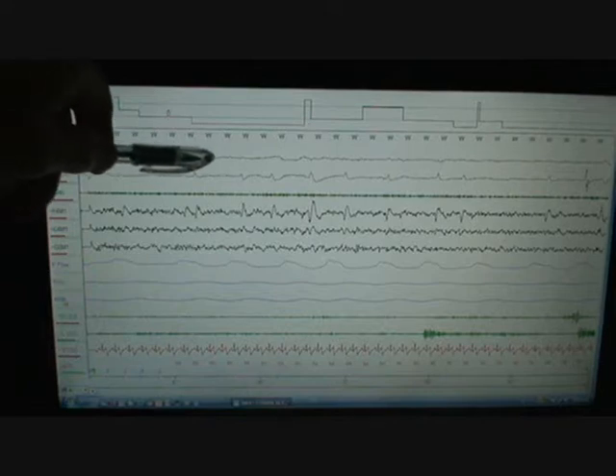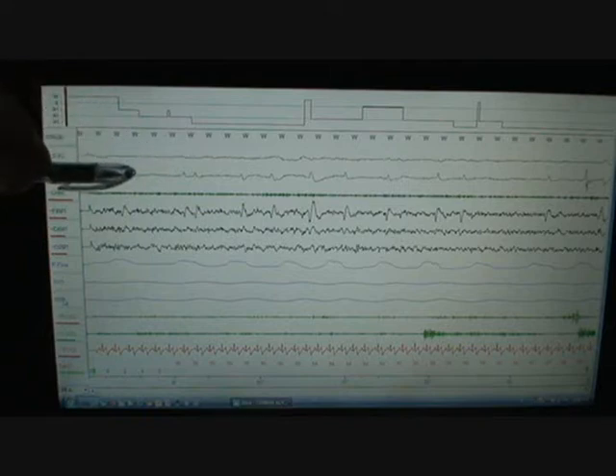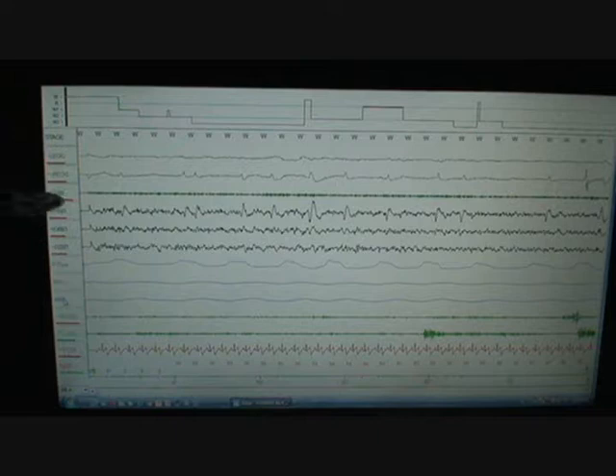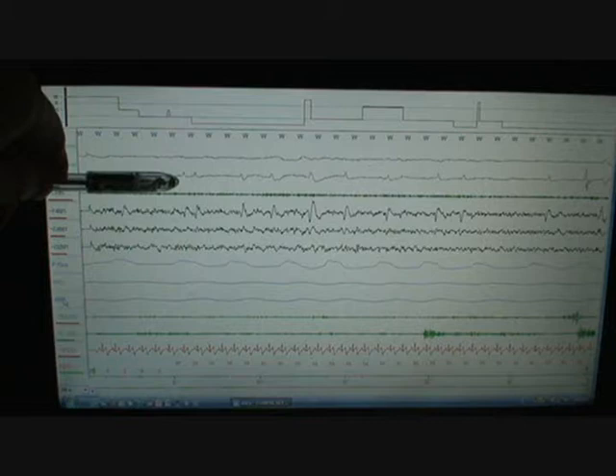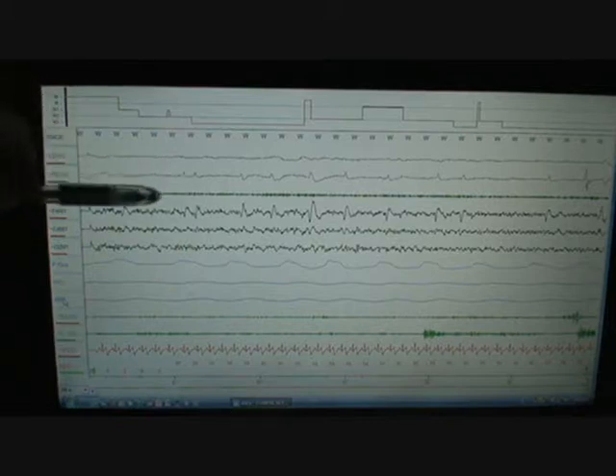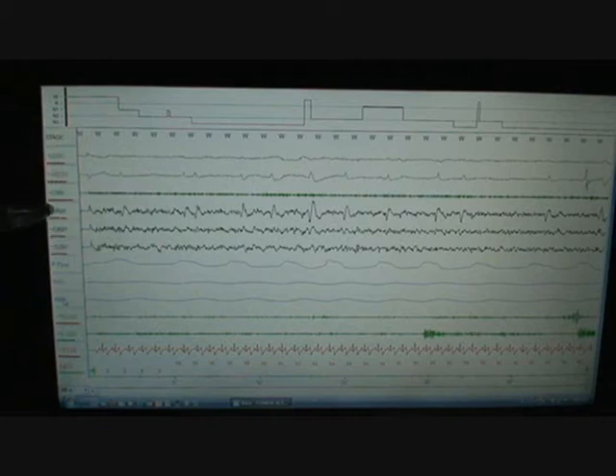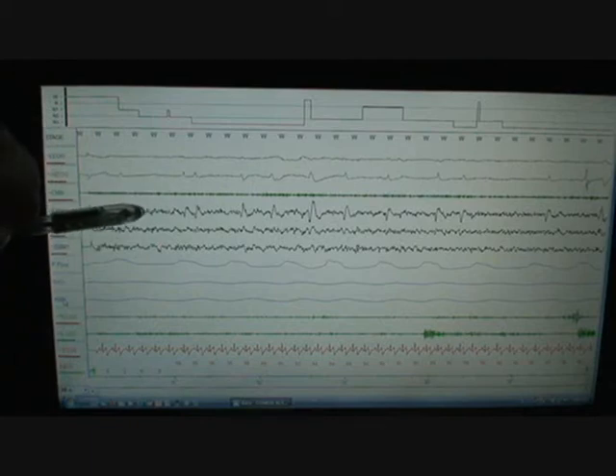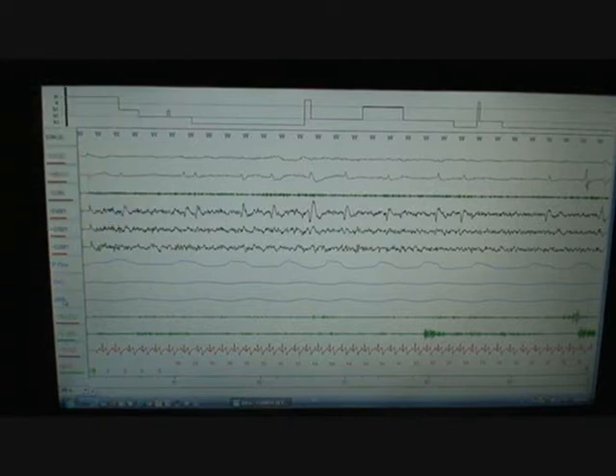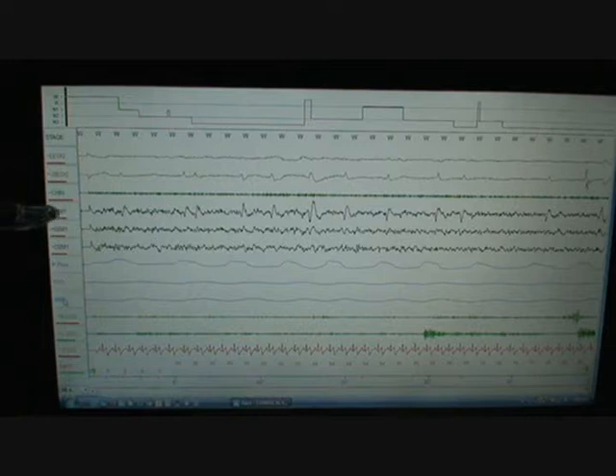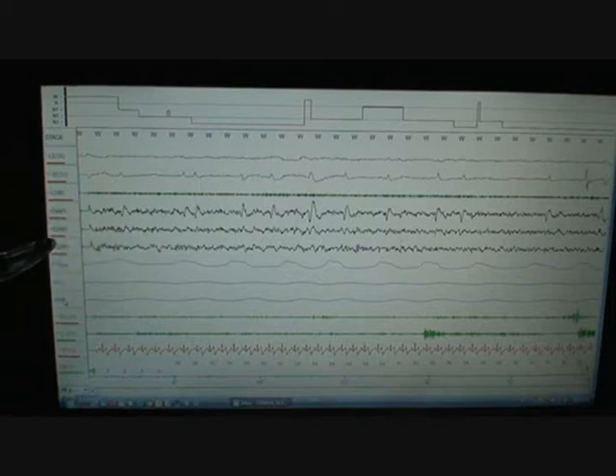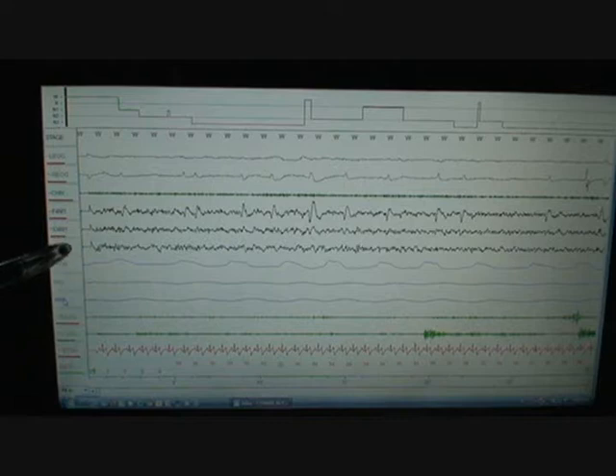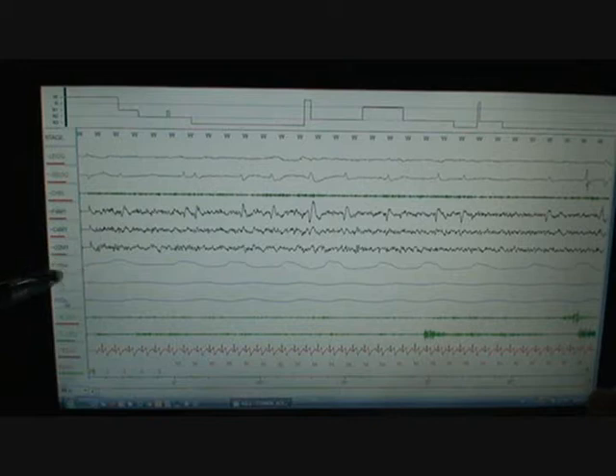This top one is the left eye, this one going across here. This one is the right eye. So you'll remember the electrodes to the either side of each eye during your study. This is the chin, the electrodes that they place either under your chin, or hopefully back near your masseters. Like when you bite down, you can feel the muscles bulge out. This is the frontal channel, placed kind of on your forehead, about at your hairline, probably about six centimeters apart. Central channels are placed kind of on the crown of your head, above your ears, about 12 centimeters in the center of your head. The occipital channels are on the back of your head.